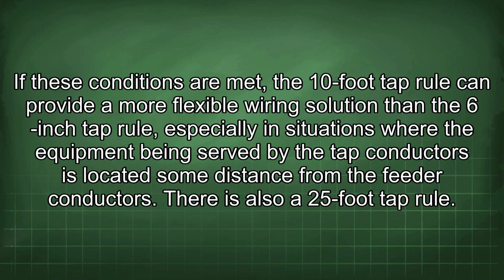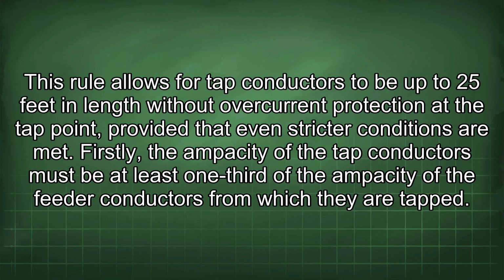If these conditions are met, the 10-foot tap rule can provide a more flexible wiring solution than the 6-inch tap rule, especially in situations where the equipment being served by the tap conductors is located some distance from the feeder conductors. There is also a 25-foot tap rule. This rule allows for tap conductors to be up to 25 feet in length without overcurrent protection at the tap point, provided that even stricter conditions are met.